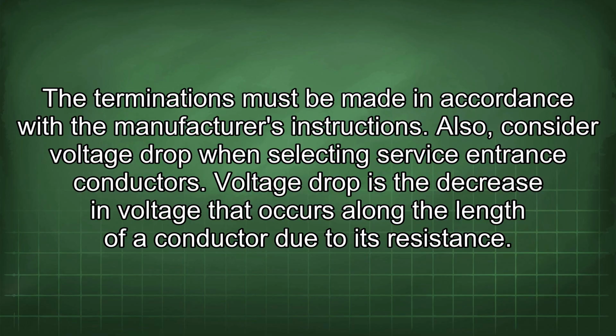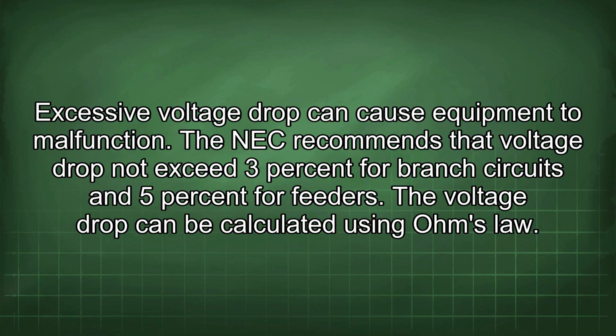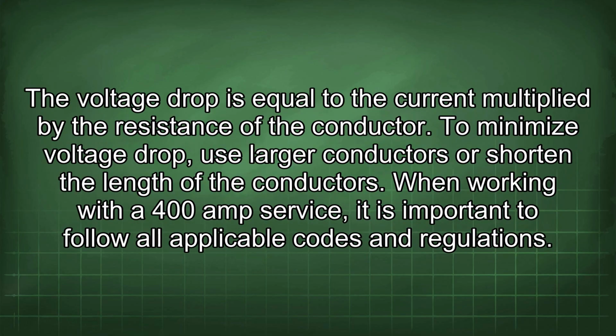Voltage drop is the decrease in voltage that occurs along the length of a conductor due to its resistance. Excessive voltage drop can cause equipment to malfunction. The NEC recommends that voltage drop not exceed 3% for branch circuits and 5% for feeders. The voltage drop can be calculated using Ohm's law. The voltage drop is equal to the current multiplied by the resistance of the conductor. To minimize voltage drop, use larger conductors or shorten the length of the conductors.